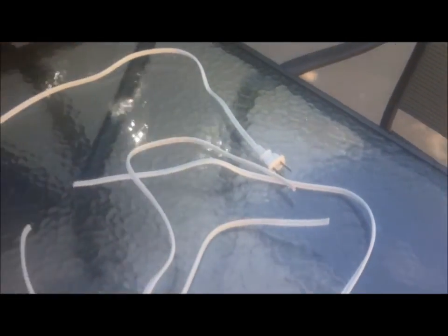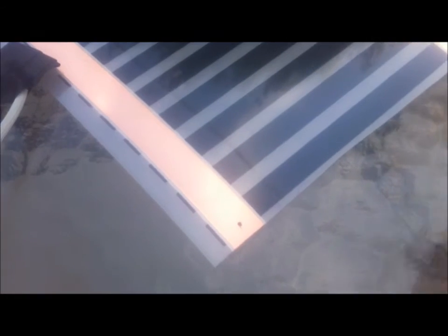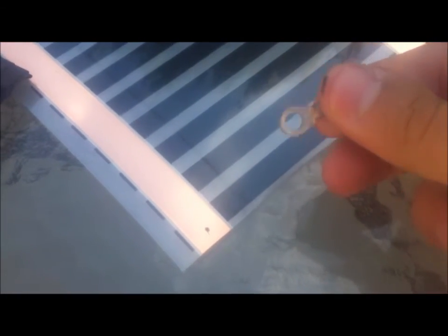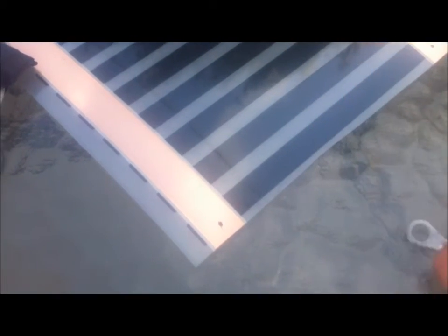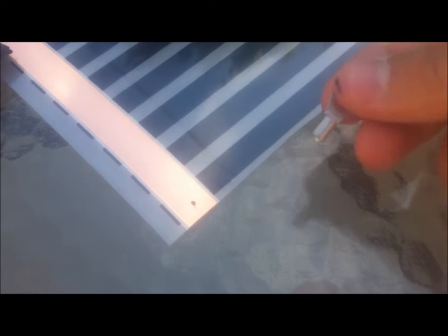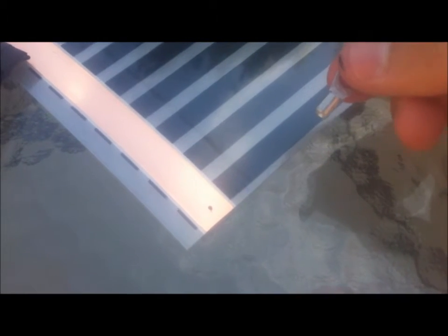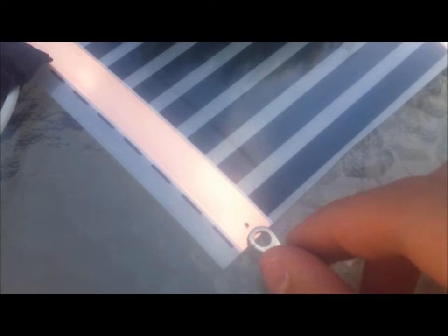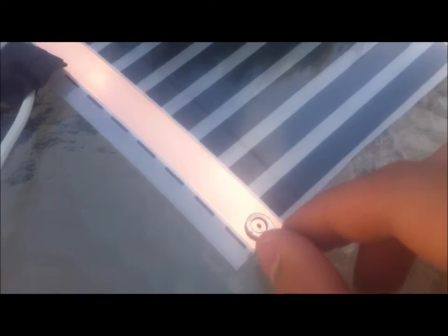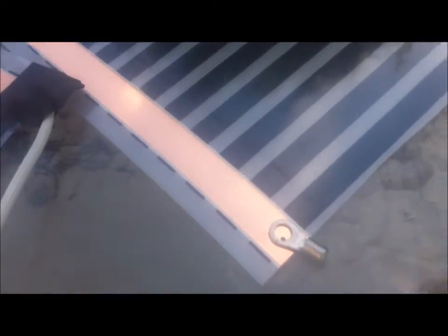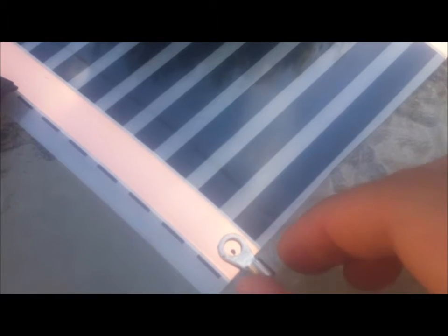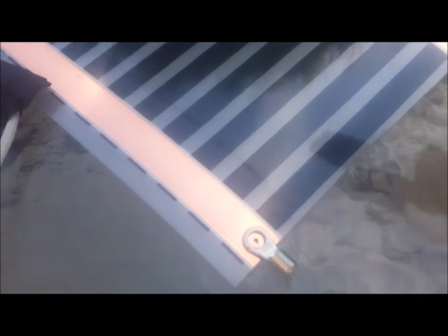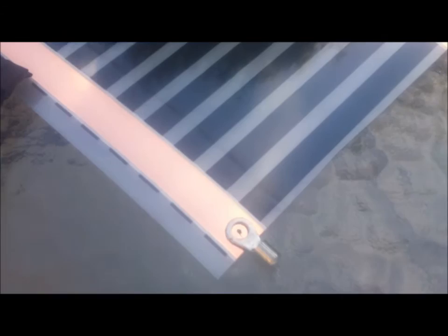So the next thing that we have to do is get the heat tape wired up. I'm using THG heat tape and it comes with these little circular things which is how you wire it up. You crimp this onto the exposed wire when you strip the extension cord, and then it's going to slide into here and then you're going to use the crimps to keep it in place. First thing you're going to do is put this here, set it at the right distance and mark it with the marker.